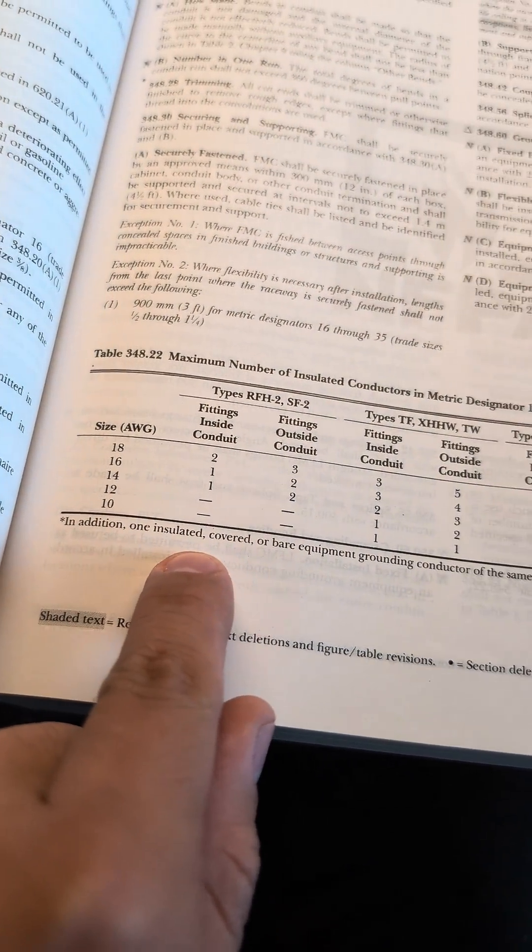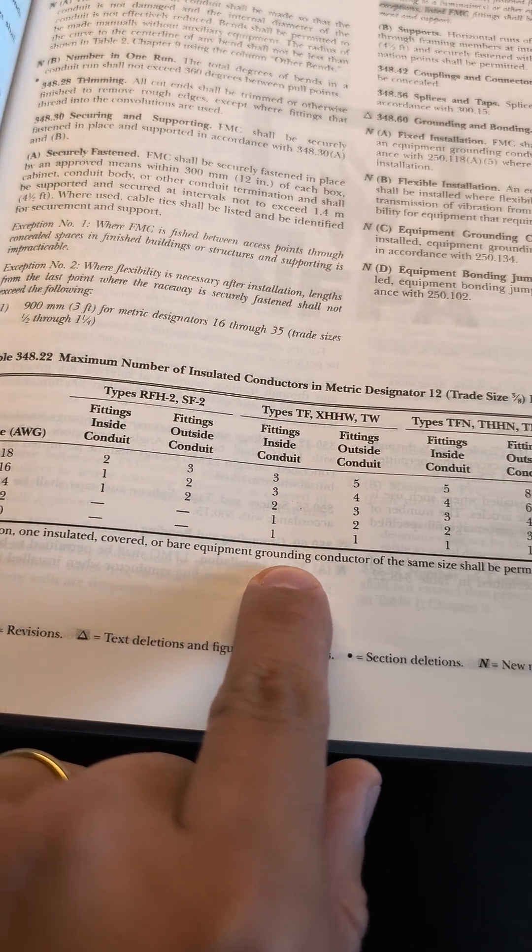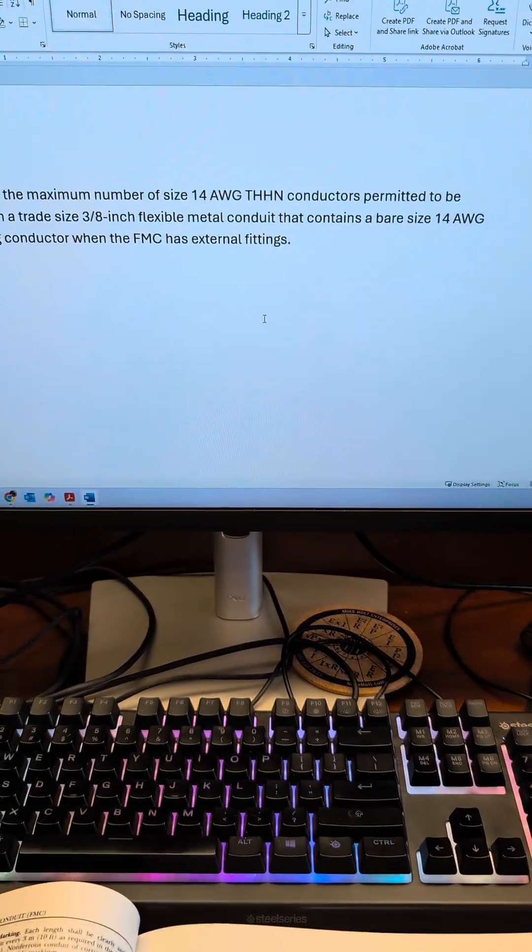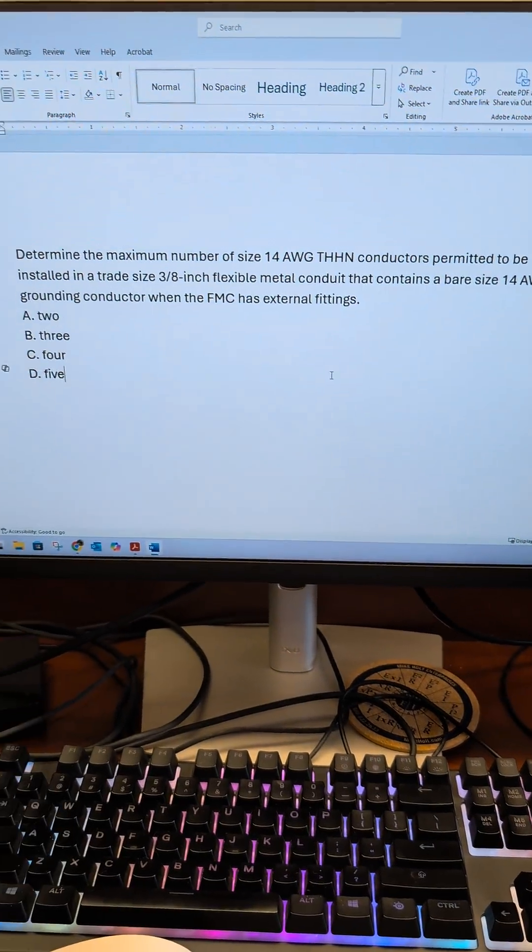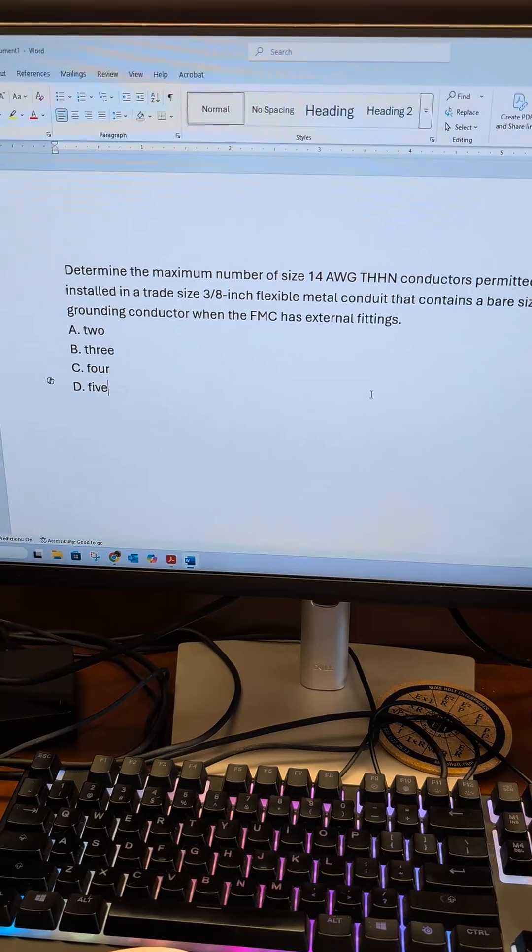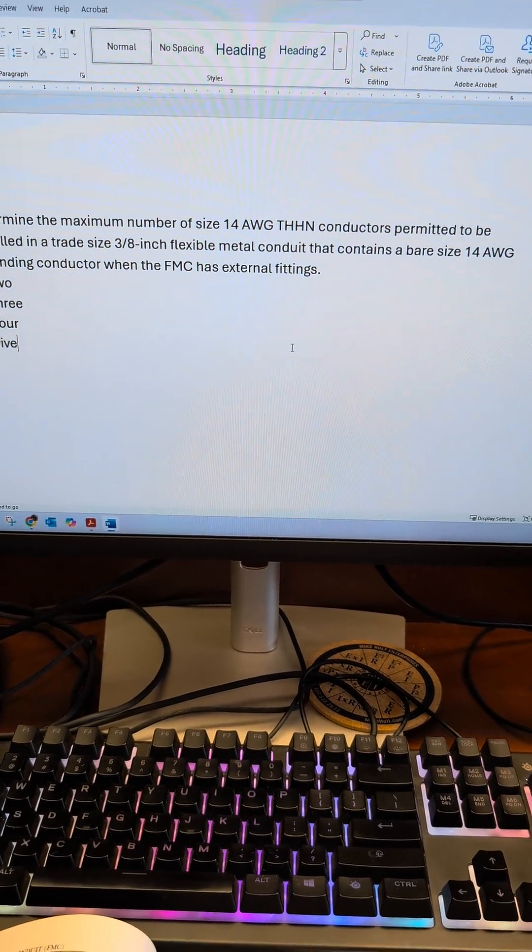In addition, one insulated, covered, or bare equipment grounding conductor of the same size shall be permitted. So we're looking for the maximum number of conductors of size 14 THHN.